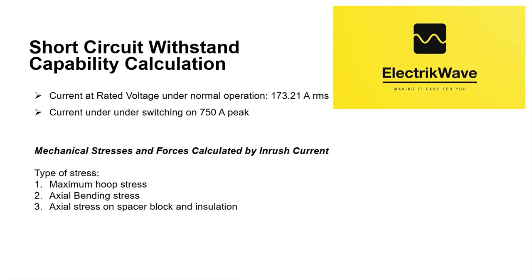Considering 120 MVAR and 400 kV, current under normal operation is 173.21 A RMS. Current under switching on is 750 ampere peak. Type of stress includes maximum hoop stress, axial bending stress, and axial stress on spacer block and insulation. Mechanical stresses and forces calculated by inrush current should not be higher than the considered strength, and there should be adequate margin between design and actual strength.